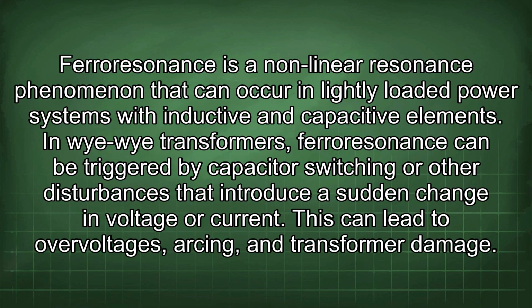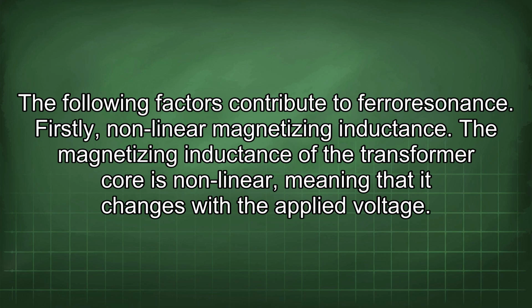Ferroresonance is a nonlinear resonance phenomenon that can occur in lightly loaded power systems with inductive and capacitive elements. In Wye-Wye transformers, ferroresonance can be triggered by capacitor switching or other disturbances that introduce a sudden change in voltage or current. This can lead to overvoltages, arcing, and transformer damage. The following factors contribute to ferroresonance.